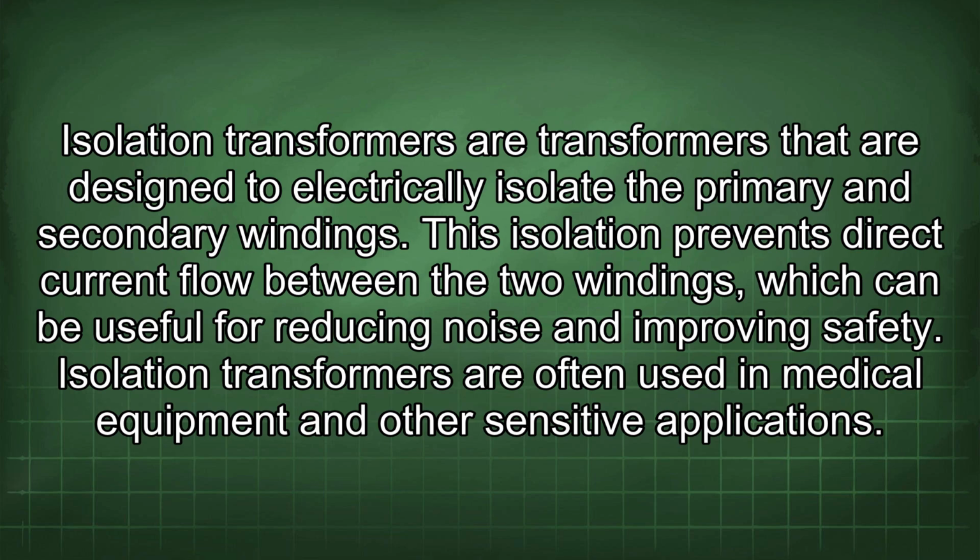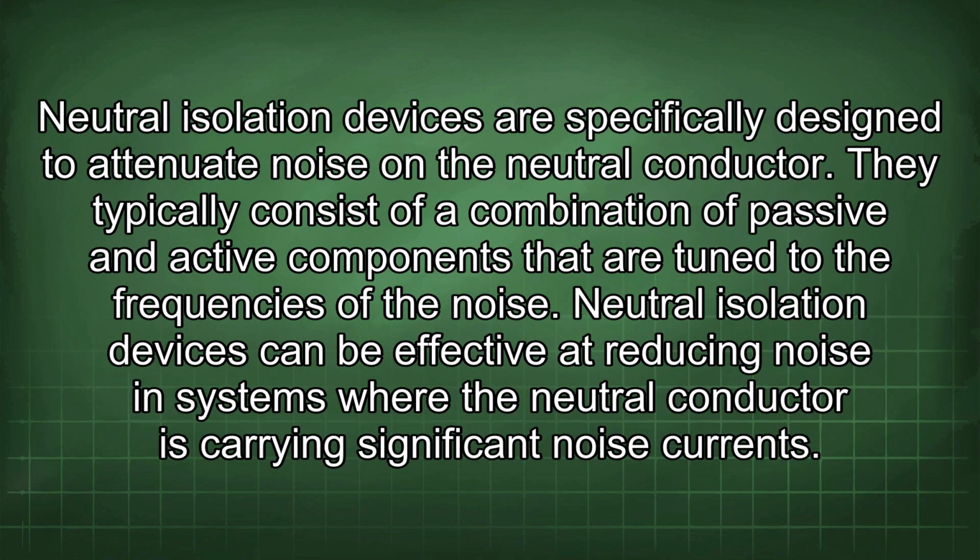This isolation prevents direct current flow between the two windings, which can be useful for reducing noise and improving safety. Isolation transformers are often used in medical equipment and other sensitive applications. Neutral isolation devices are specifically designed to attenuate noise on the neutral conductor. They typically consist of a combination of passive and active components that are tuned to the frequencies of the noise. Neutral isolation devices can be effective at reducing noise in systems where the neutral conductor is carrying significant noise currents.